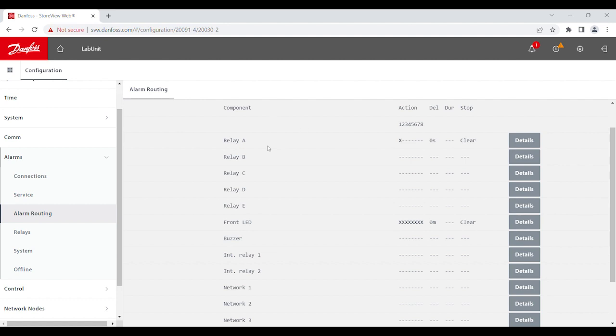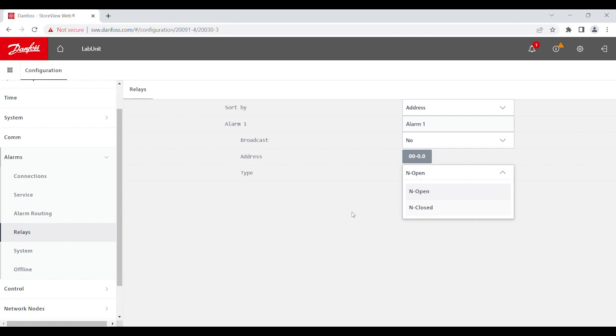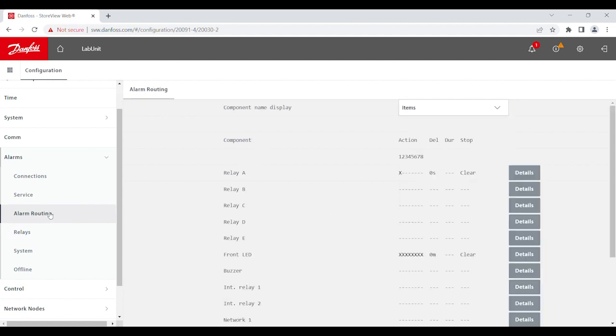Now, once you have enabled the relay, you can head over to the relay section. And you will notice that the alarm relay has been generated. Now, you get to assign the address here and also the type, whether it be normally open or normally closed. So, any time there is an alarm for your action number one, then it will generate the relay that's been just created.